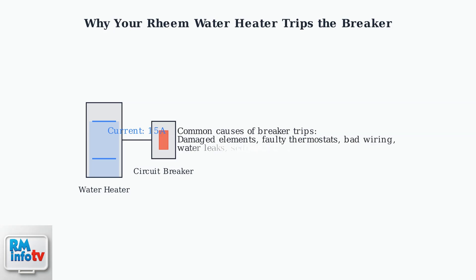Finally, if the circuit breaker is undersized for your water heater's electrical demands, it will trip even during normal operation. The breaker rating must match the heater's requirements. These six causes represent the most common reasons why your water heater trips the circuit breaker.